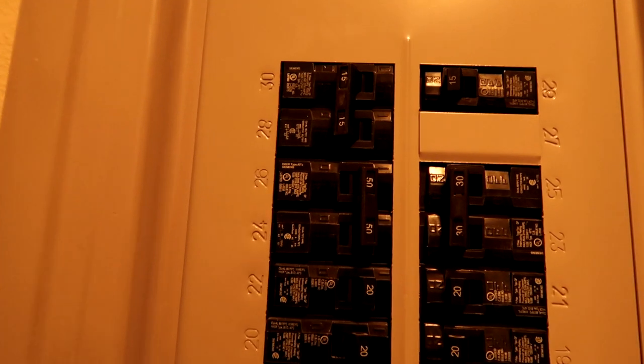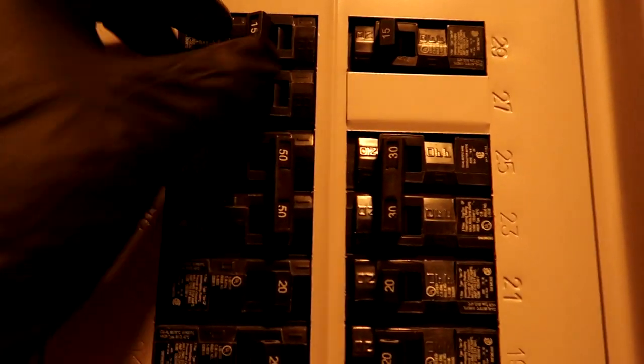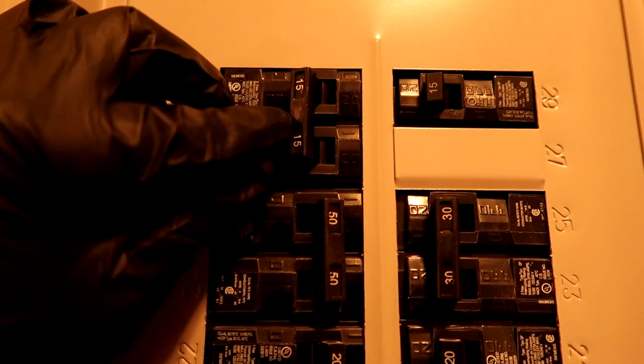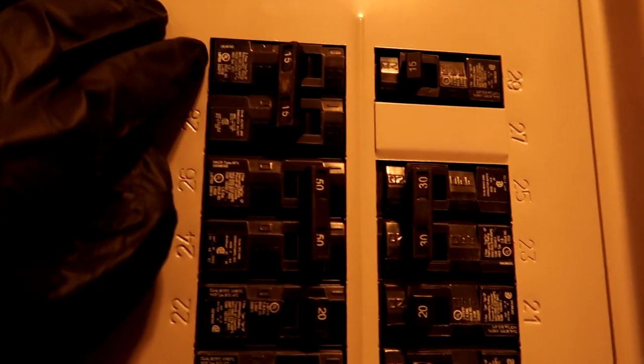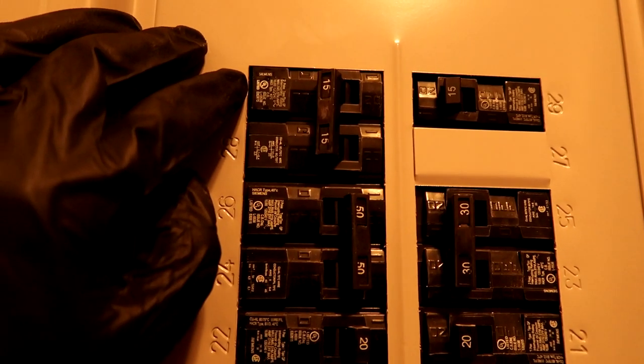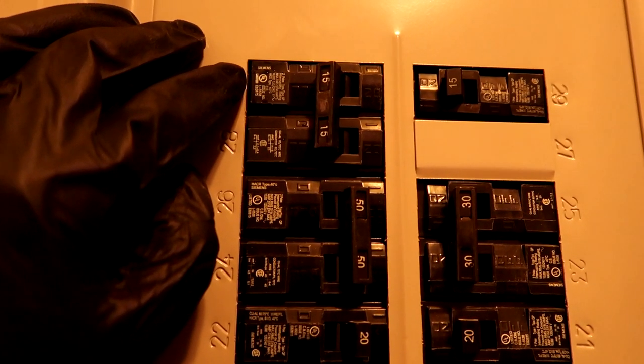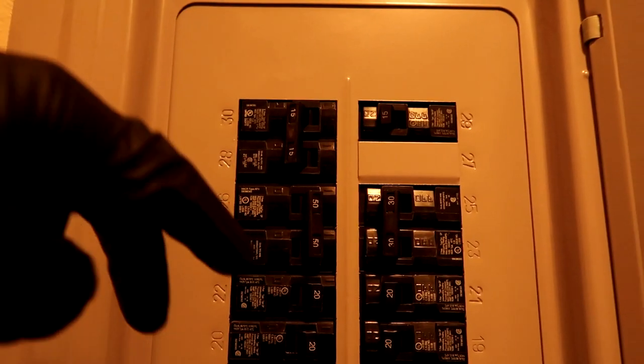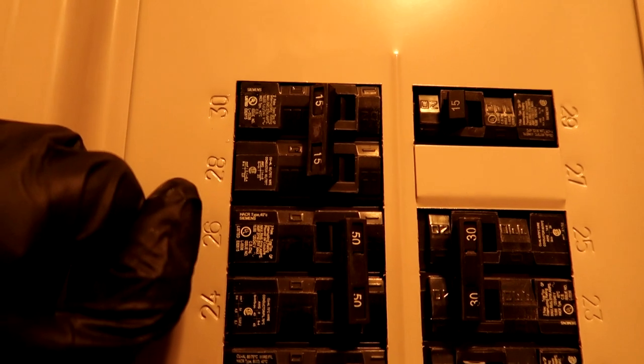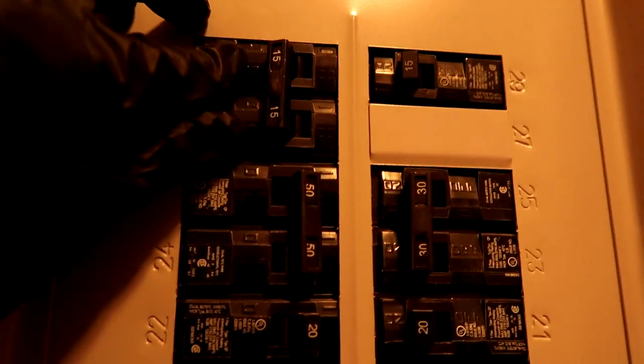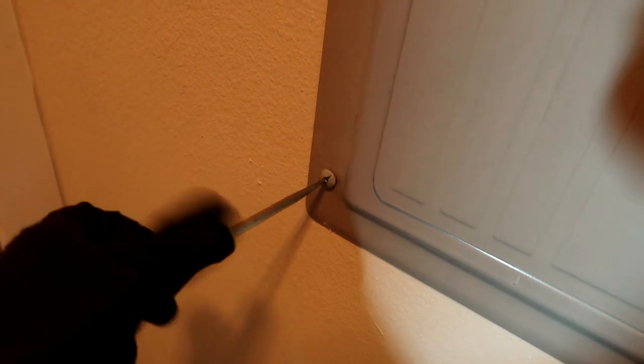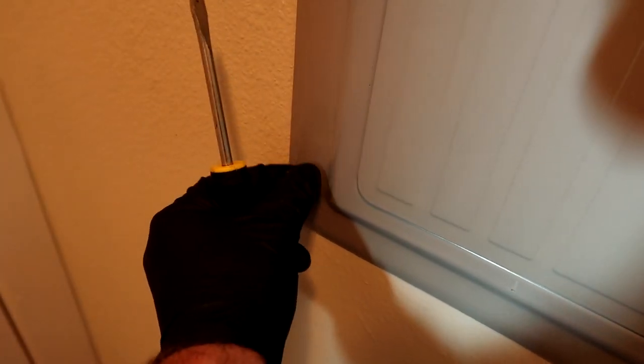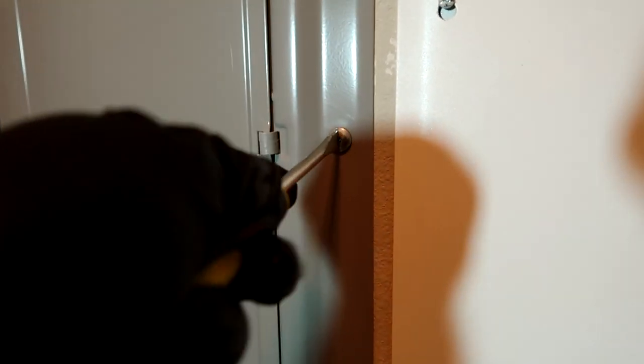All right, I pulled the disconnect. See what happens. Might have a bad breaker, big dog. The disconnect is pulled, so it's not even making it out to the condenser. It hits the disconnect and it's not even making it out to the condensing unit. Let me take this panel off. I wonder if this breaker is bad. Yeah, I pulled the cover off the disconnect, all the wires look good in there, nice and tight. So power's not even going to the condensing unit and the breaker's still tripping. So I'm going to take all these screws off, pull this breaker panel off.